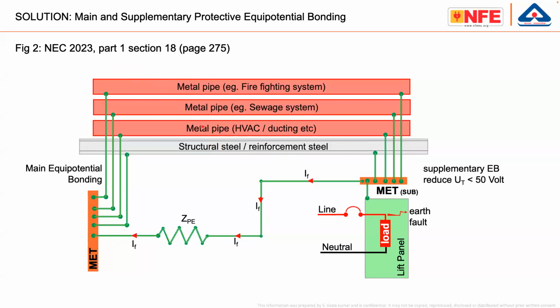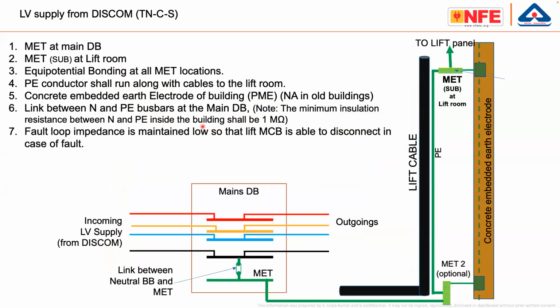Now, let us look at how this has to be implemented in a proper TNCS network supplied by a distribution company, a low voltage supply to a consumer premise. Legally, the distribution company is supposed to give you TNCS, but unfortunately, they don't give it. But we will see it in the next slide. So if it is a TNCS network, you can see here the main distribution board of the building, the main supply to the lift. You see four wires: the three-phase and neutral come from the distribution company. Now, there is a link between neutral and earth at the main distribution board. We are converting TNC to TNCS.